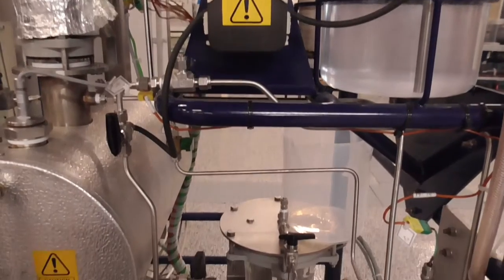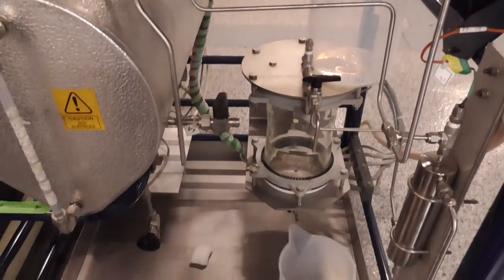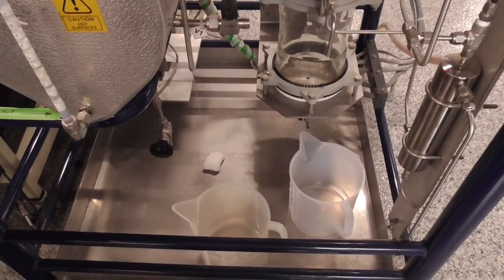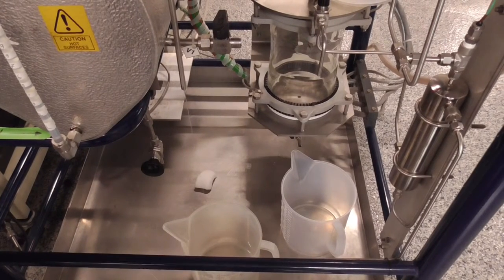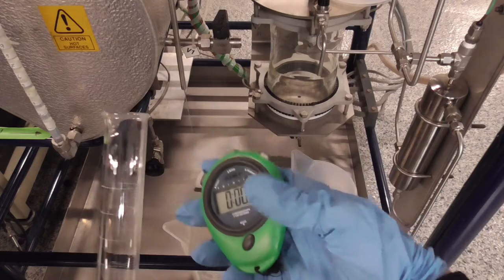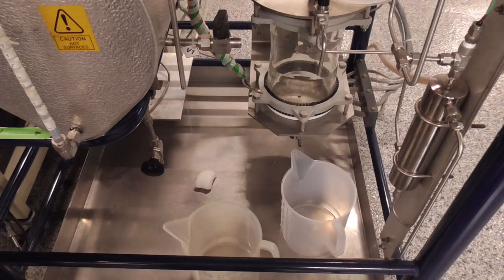Once you have the RPM set on the computer, alcohol should start flowing out of this calibration tubing, and you have a graduated cylinder and stopwatch for determining the flow rate as a function of RPM. You don't need a standard curve so much as determine at what RPM you get 30 mils per minute, as this is the flow rate we run at generally.